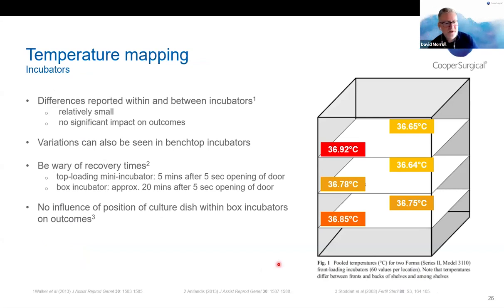Just some examples then. This is taken from a paper by Walker and colleagues from a decade or so ago. And what this showed is in a typical box incubator, they actually tested 2 Forma box incubators. And what they reported is that depending on where they tested, they got slightly different temperatures. So you can see front left was 36.92, but it could get as low as 36.64 at the back of the middle shelf. So just really to show that there will be small differences across incubators. We also see it to some extent in bench tops, less, but still possible.